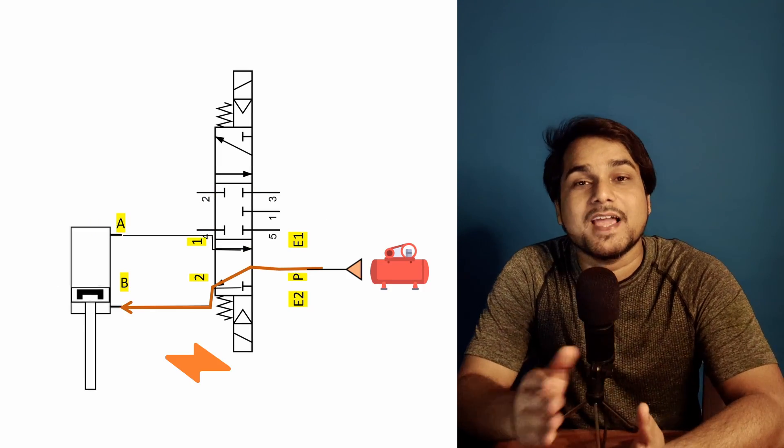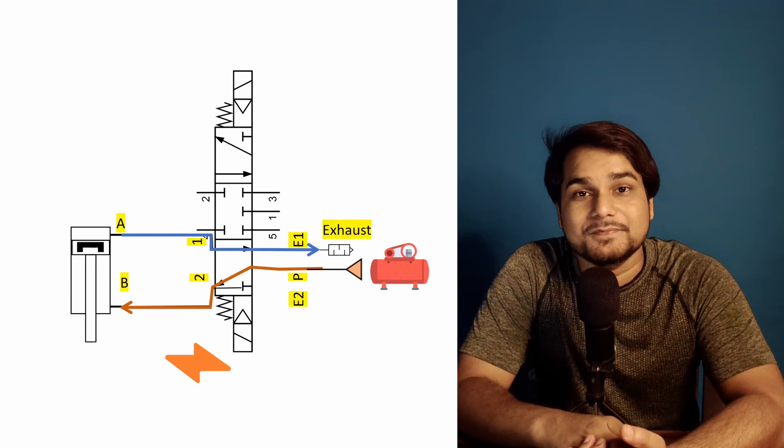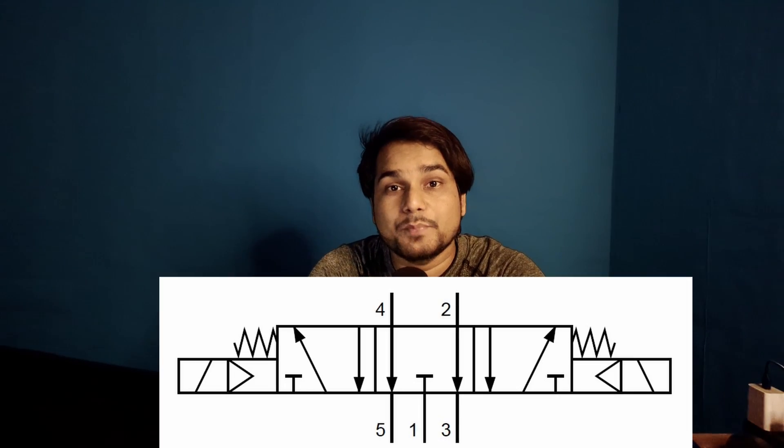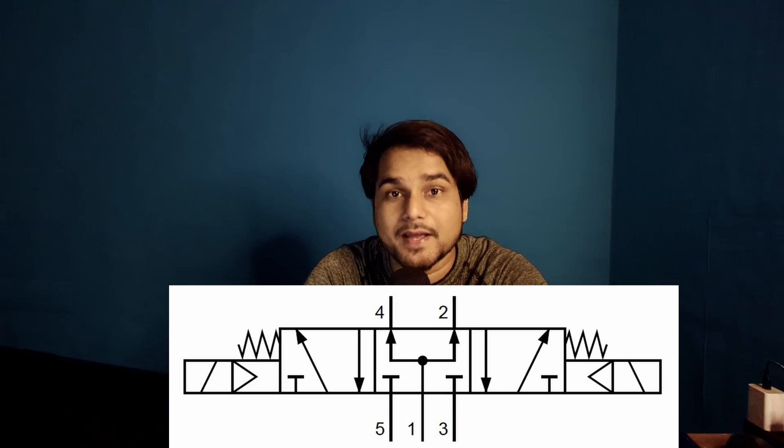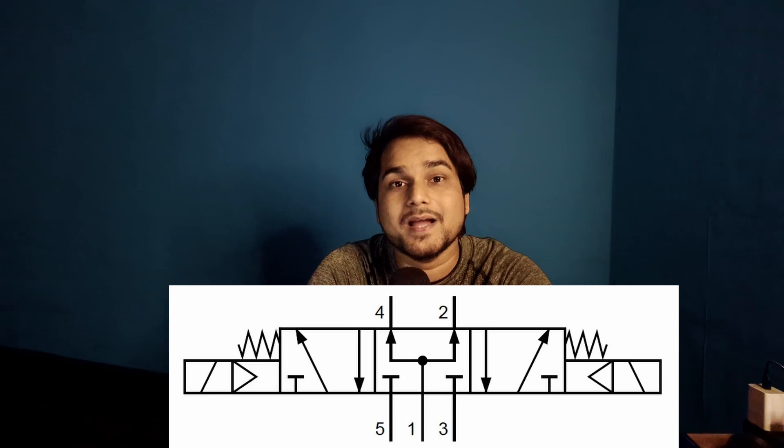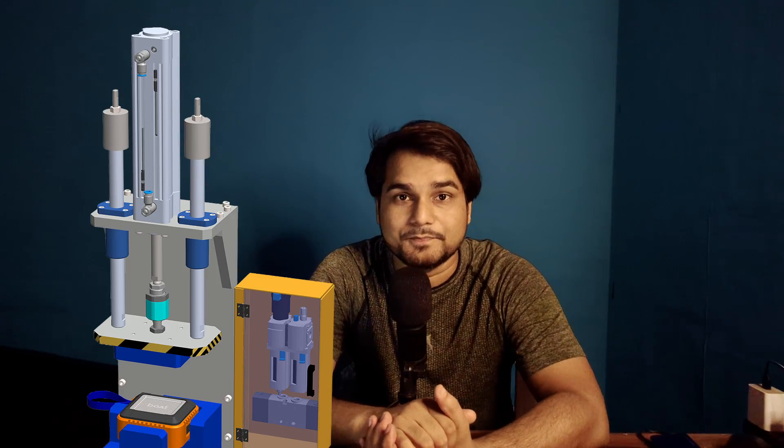To move the cylinder, we activate the appropriate solenoid. As a side note, 5/3 solenoid valves always come in double coil — not single coil. The 5/3 valve also comes in two additional varieties: center port open and center port pressure. You can use the 5/3 center open to free the pressure within the pneumatic circuit, and the 5/3 center pressure to balance the force within the pneumatic cylinder. These variants are not applicable for this press system and will be covered in upcoming projects.